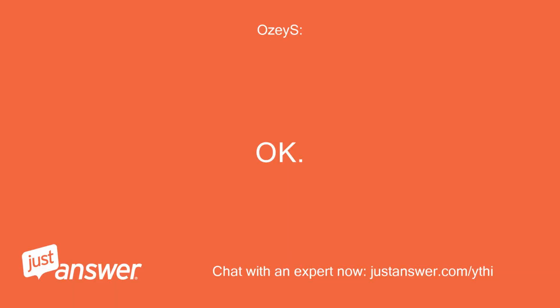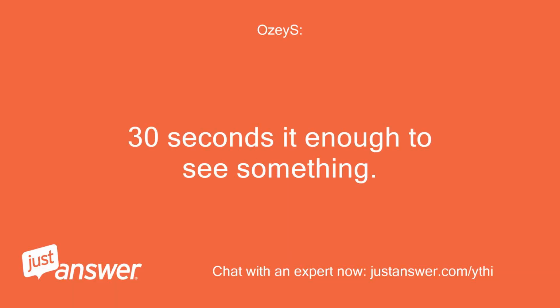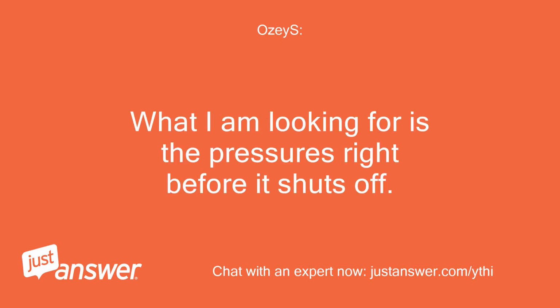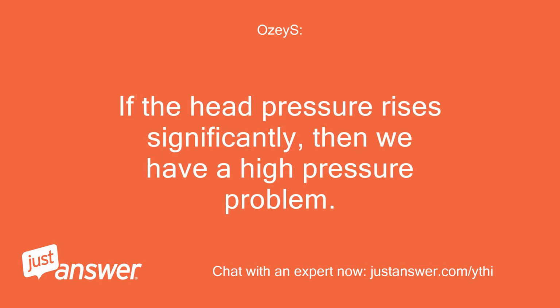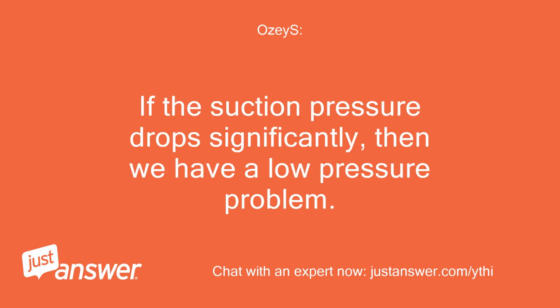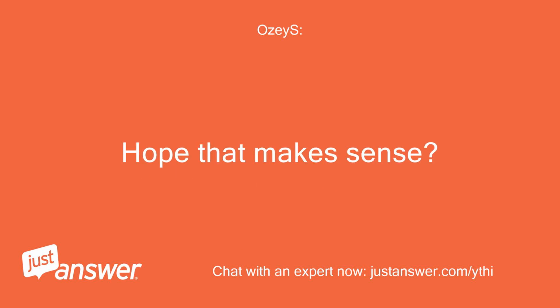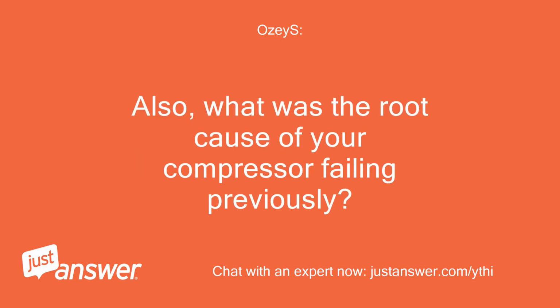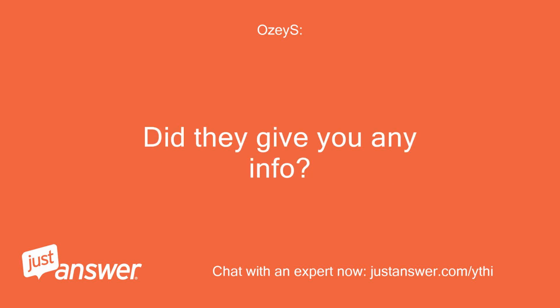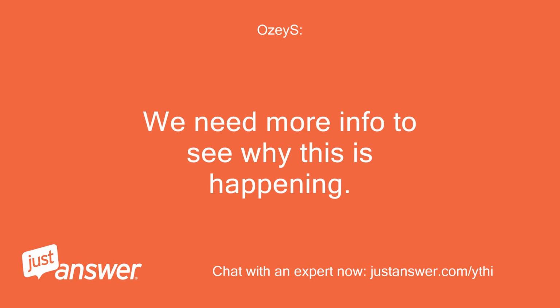Okay. 30 seconds is enough to see something. What I am looking for is the pressures right before it shuts off. If the head pressure rises significantly, then we have a high pressure problem. If the suction pressure drops significantly, then we have a low pressure problem. Hope that makes sense. Also, what was the root cause of your compressor failing previously? Did they give you any info? We need more info to see why this is happening.